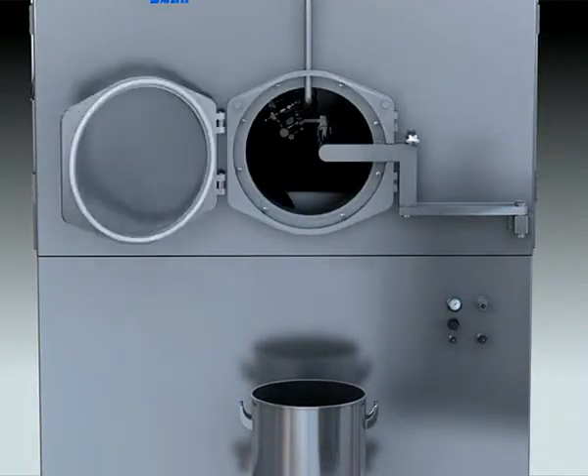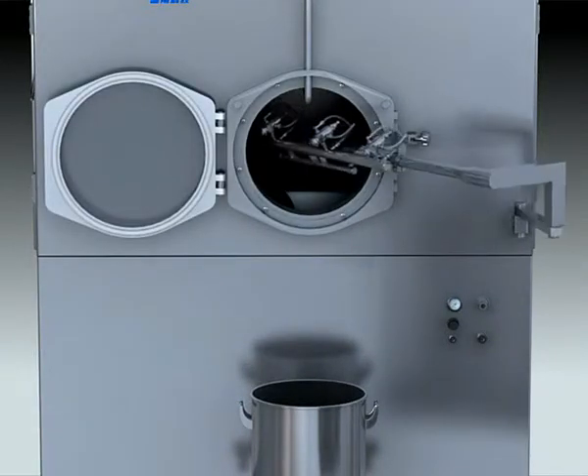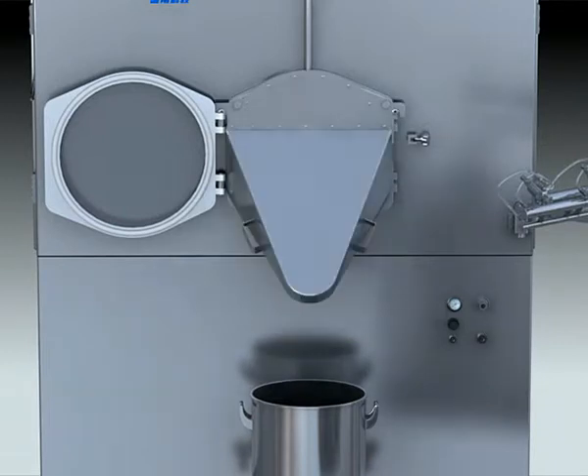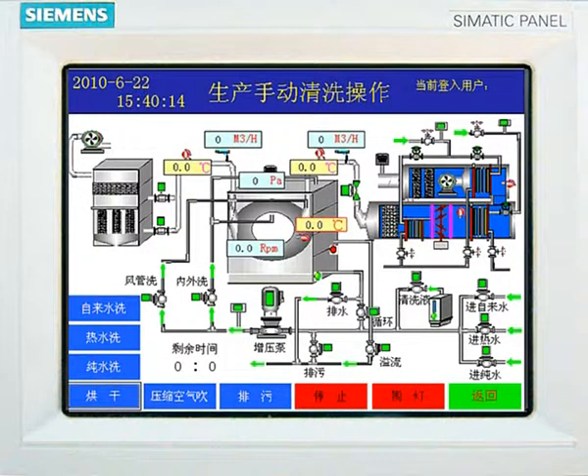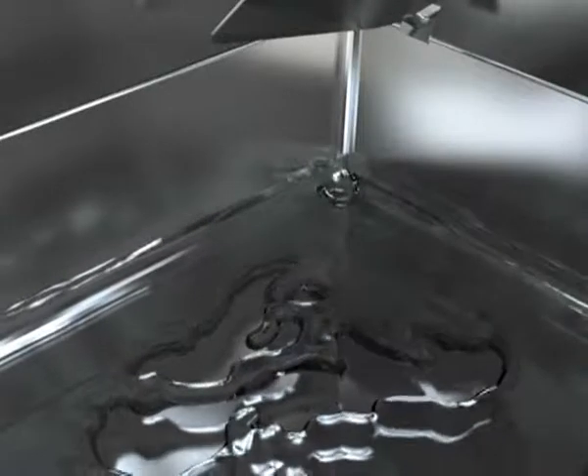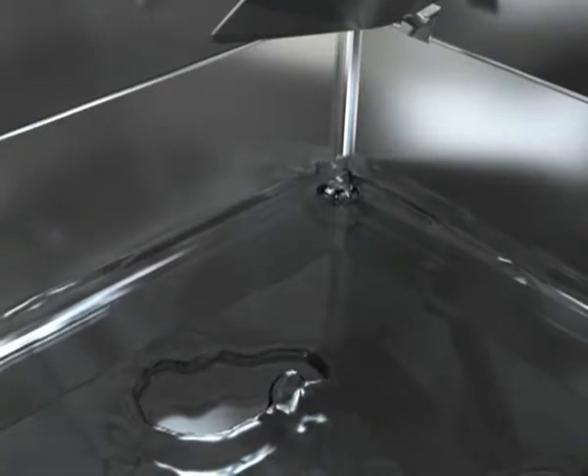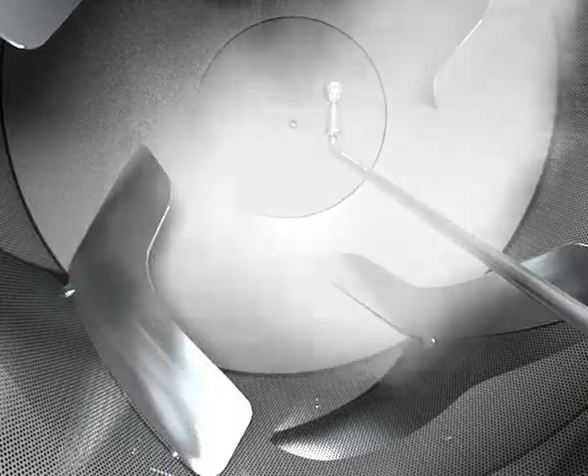After coating process, switch on WIP system. Wash the coater with tap water, washing detergent, and pure water. After which, turn on drain valve. Start pipe reverse blow and finish washing process. Then start hot air drying stage. Set inlet air temperature and begin the process. Cool air is sucked in by blower through filter and heat exchanger, and then blows hot air in the coater chamber. The air is exhausted by air exhaust valve at both sides. After drying, the machine stops working.